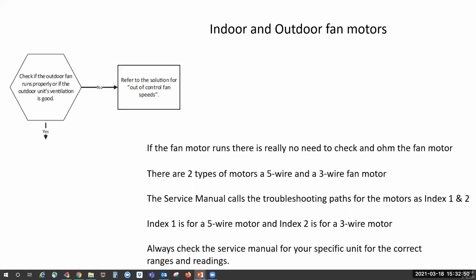Checking your fan motor. There are two types of fan motors, and this kind of threw a few people for a loop, so I'll just give you a heads up. This is a test question. There are two types of fan motors, a 5-wire and a 3-wire fan motor. If the fan starts, there's no need to even troubleshoot it any further. You want to check it, see if it spins freely. If it does not, obviously you want to replace it. If it does run, there's no need to ohm it out. You know it's being told to come on voltage-wise, so you just want to move on.